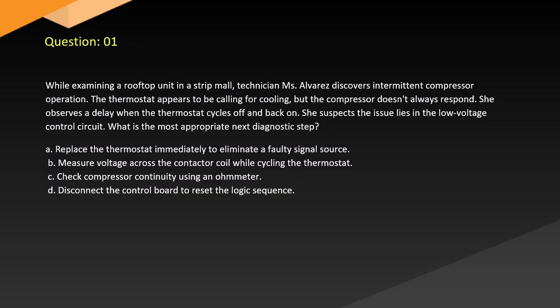Question 1. While examining a rooftop unit in a strip mall, technician Alvarez discovers intermittent compressor operation. The thermostat appears to be calling for cooling, but the compressor doesn't always respond. She observes a delay when the thermostat cycles off and back on. She suspects the issue lies in the low-voltage control circuit. What is the most appropriate next diagnostic step?